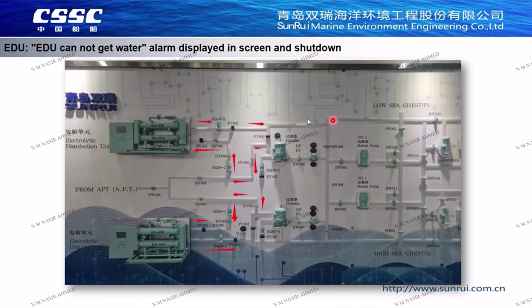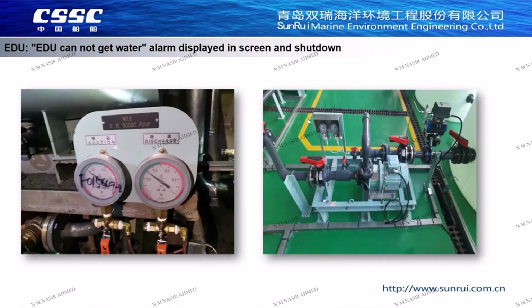If EDU can not get water, first check the pipeline is unblocked, or whether some manual valves along the pipeline are not opened. Secondly, observe the working condition of booster pump. Check whether pressure gauge fluctuates and pressure value is stable. Check whether pump pressure could be built to transit the seawater.